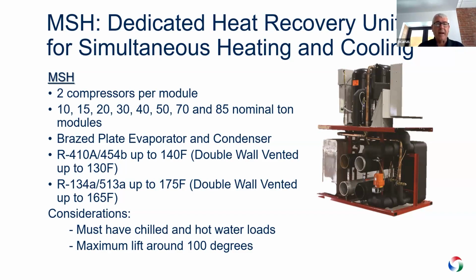The key consideration here is, in order to do heat recovery, you must have a chilled and a hot water load. It's really important that you understand, as well as possible, because it's a difficult ask, what's the heating load and what's the cooling load, so that we can properly control the system and deliver the most amount of heat recovery that we can possibly do. Maximum lift in that application, about 100 degrees.